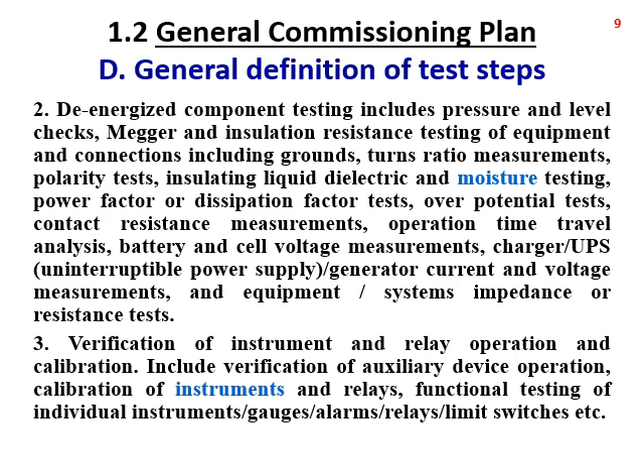Number 3. Verification of instrument and relay operation and calibration, including verification of auxiliary device operation, calibration of instrument and relays, functional testing of individual instruments, gauges, alarms, relays, limit switches, and other components.